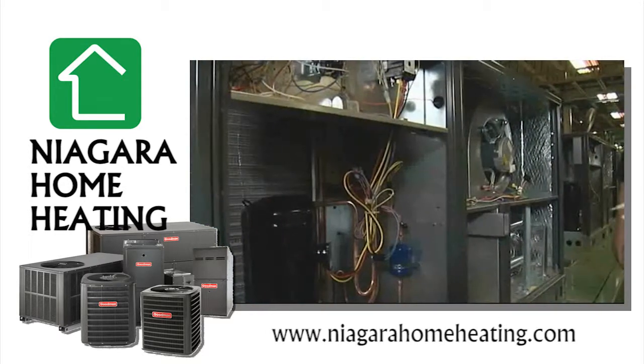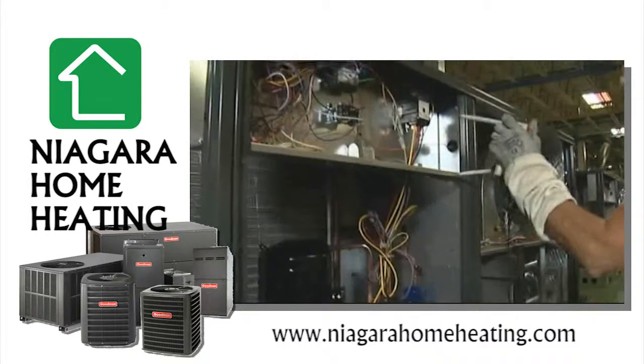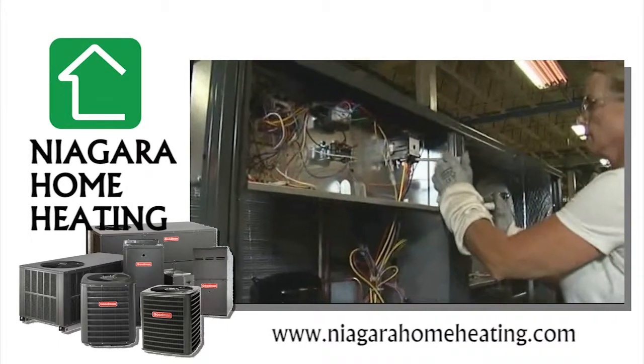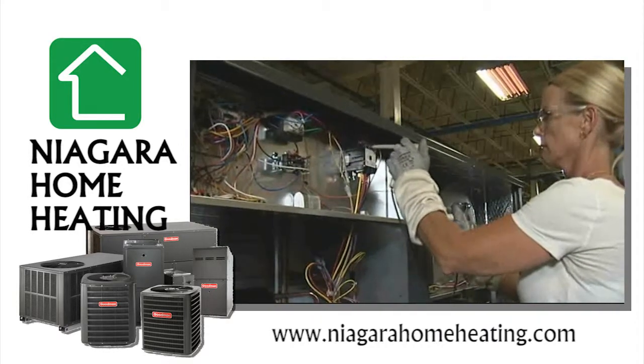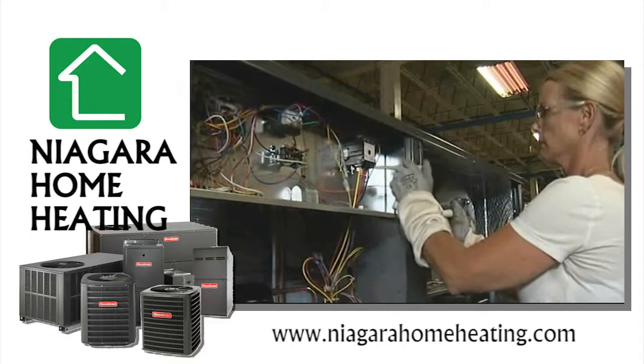Okay, Mark, we're at the run test station, and this operator is our run tester. Right now she's doing a hi-pot test, which is a high voltage, low current test to make sure there's no loss to ground. There's no shorts in the unit anywhere.